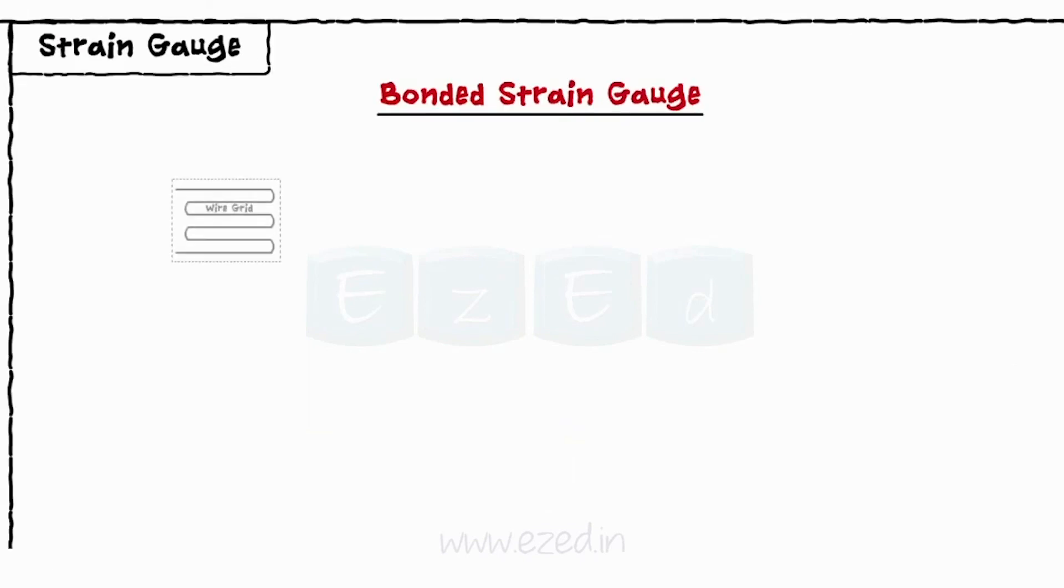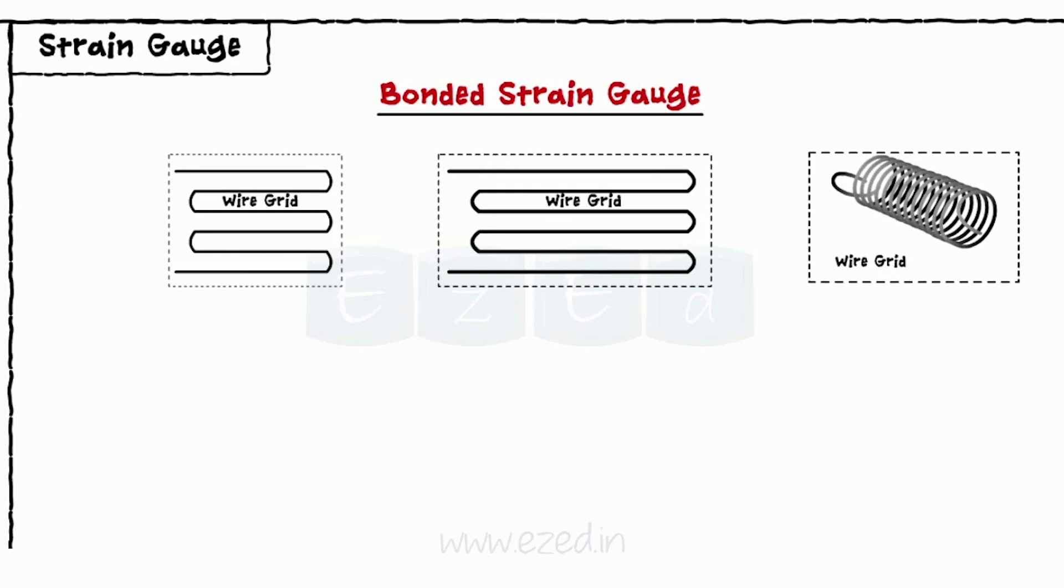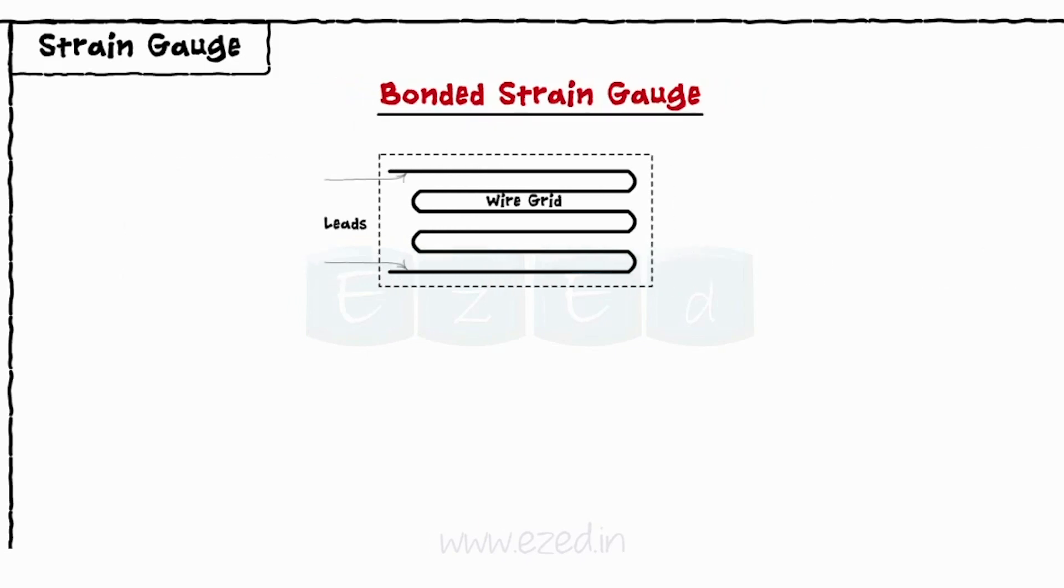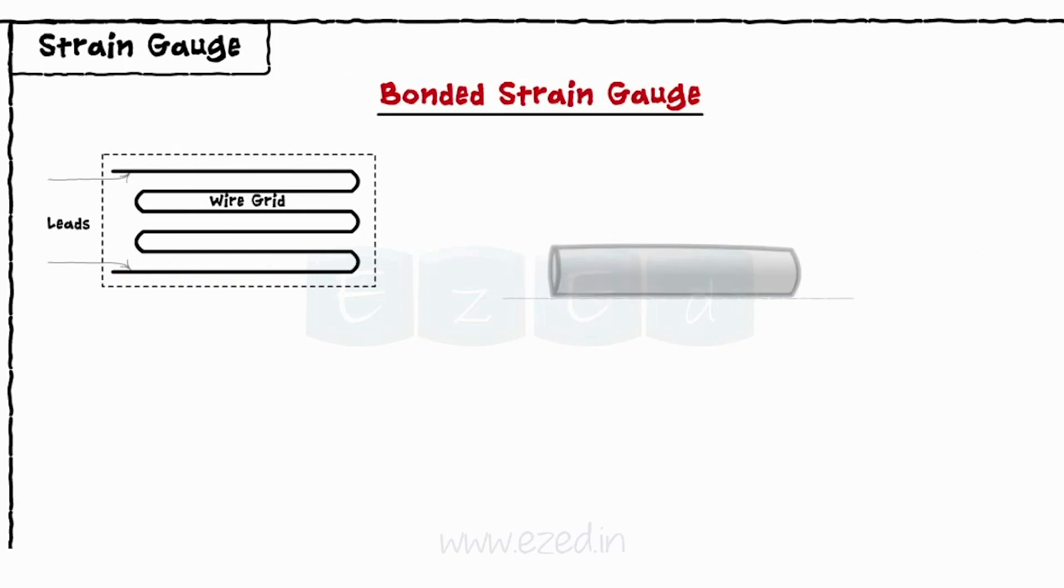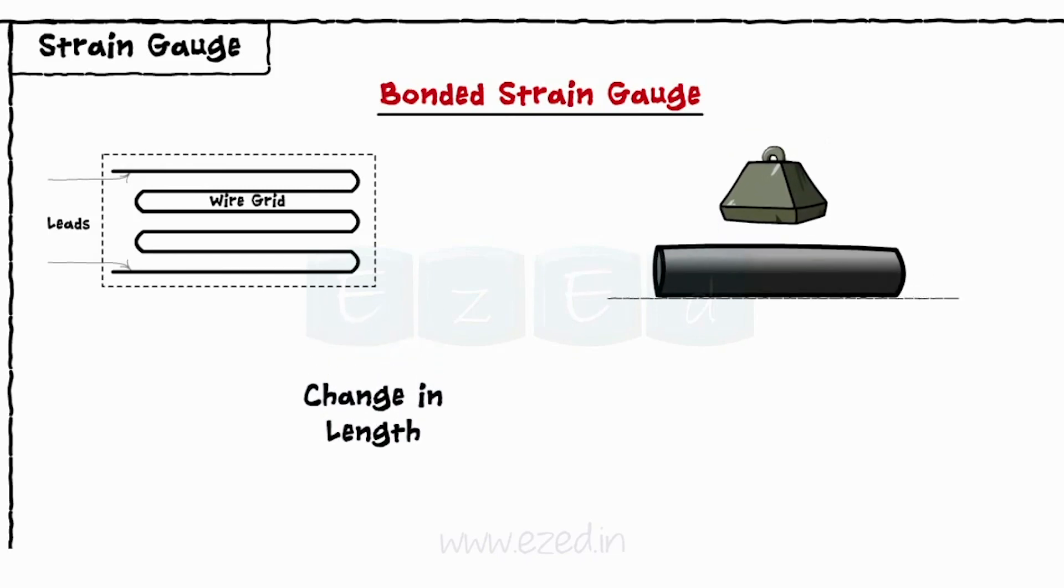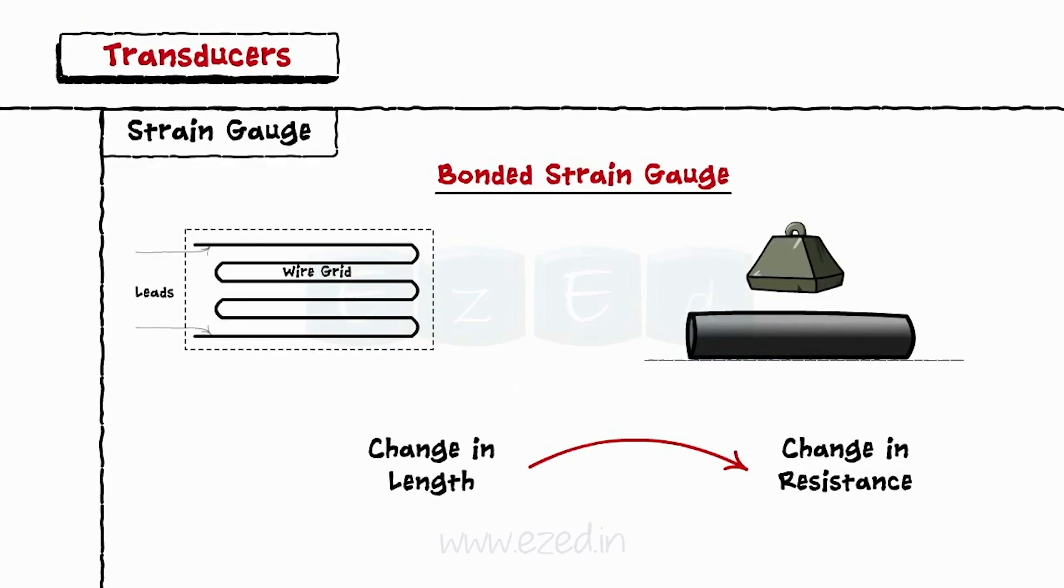These gauges are bonded with cement to the surface. The shape of the wire grid can be square, rectangular, circular etc. Bonded strain gauge has two leads for external connections which are isolated from each other. As the gauge wire changes its length, its resistance changes and corresponding change in resistance gives us the required output.